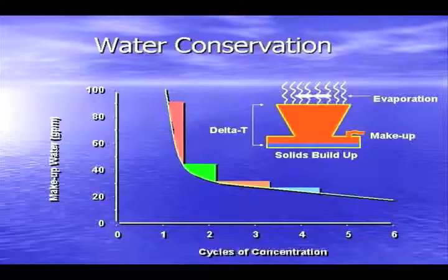One of the topics I'm going to spend a couple slides on is what we call concentration ratio, or cycles of concentration. The more you can concentrate that water — because steam is leaving the tower at the top, so all the minerals stay behind — the more you can cycle that up, the less water you're going to use. And it's pretty drastic.